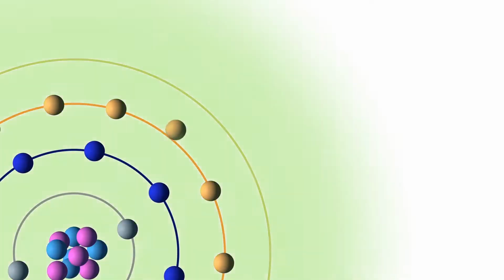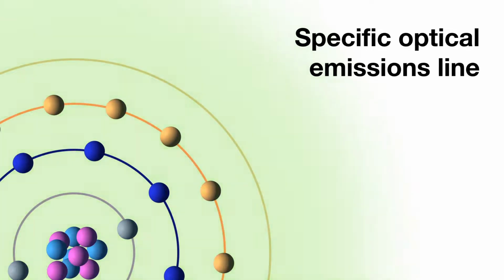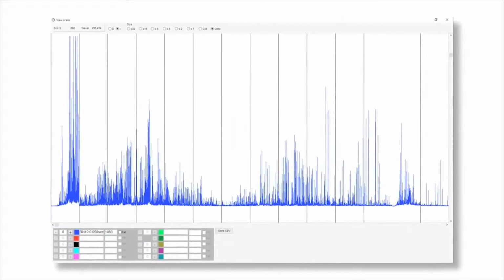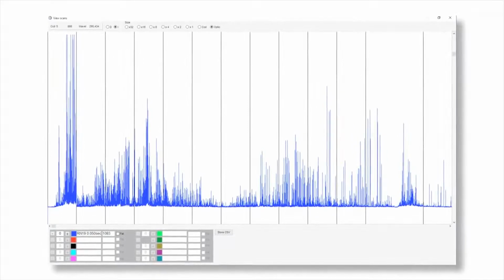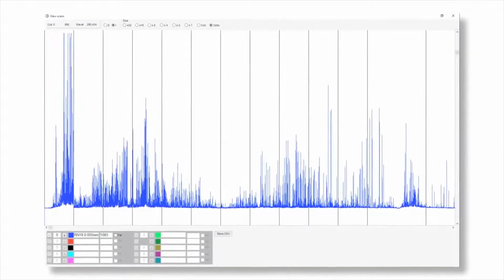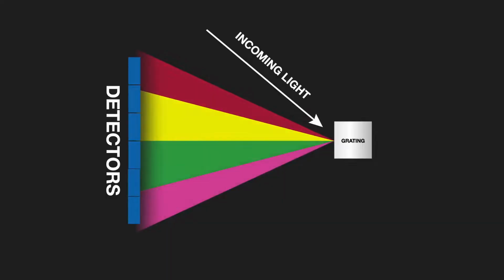Every element emits a series of spectral lines corresponding to the different electron transitions between the different energy levels or shells. Each transition produces a specific optical emission line with a fixed wavelength or energy of radiation. For a typical metallic sample containing iron, manganese, chromium, nickel, vanadium, etc., each element emits many wavelengths, leading to a line-rich spectrum. For example, iron emits just over 8,000 different wavelengths, so choosing the optimum emission line for a given element in a sample is important.